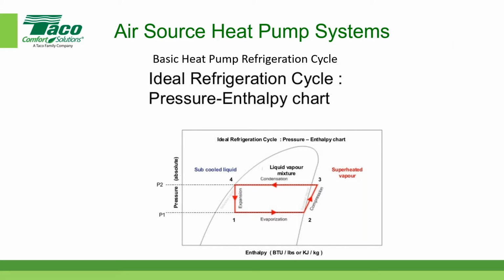Well, enthalpy is the total energy of the fluid. In other words, it's in BTUs per pound, if it's in the imperial units. So enthalpy is always BTUs per pound. It's the total energy of the working fluid. And this is called a pressure enthalpy diagram. So the horizontal lines are constant pressure, the vertical lines are constant enthalpy lines.